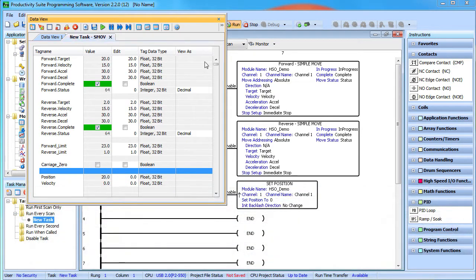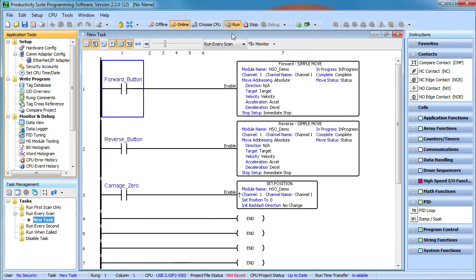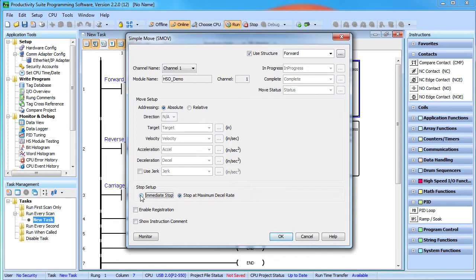Now what happens if I push the forward button but let go before it finishes the move? Well look, the motion stops immediately – why? Because we told it to. You can see that over here. If we had checked this button, then it would have decelerated to a stop at the max rate specified in the hardware setup.